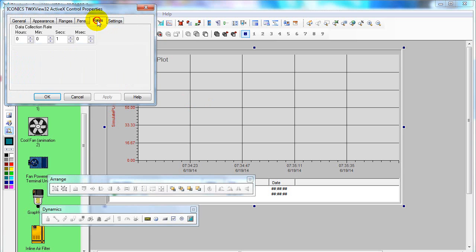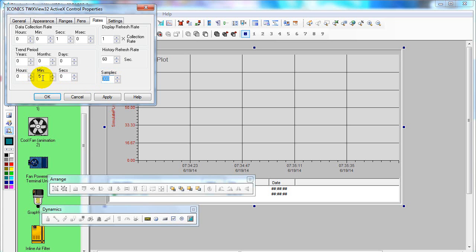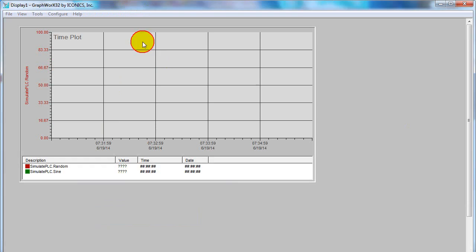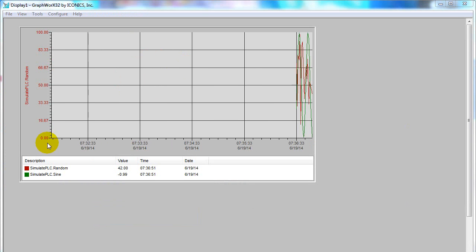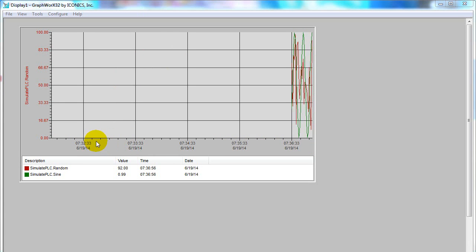You can configure the rate. The default rate is one second, and the trend period default is two minutes. You can change it to five minutes. When you change the trend period, the sample rate changes accordingly. Click Apply and OK, then get back to runtime. The trend period will change from two minutes to five minutes.